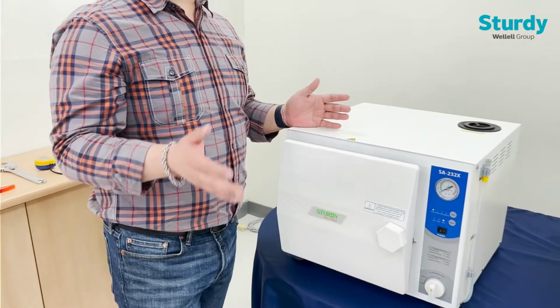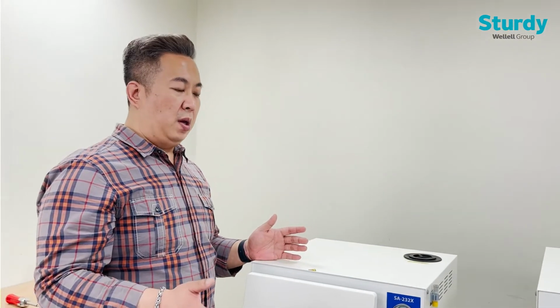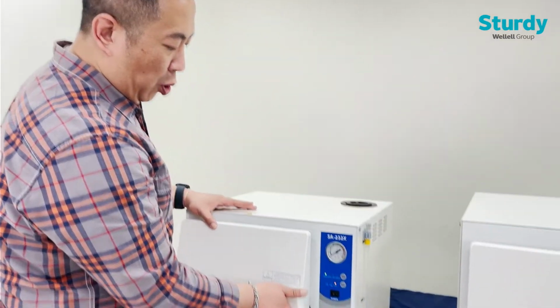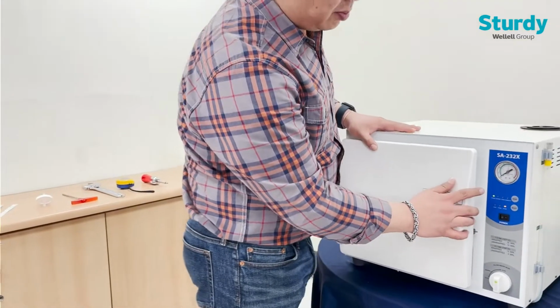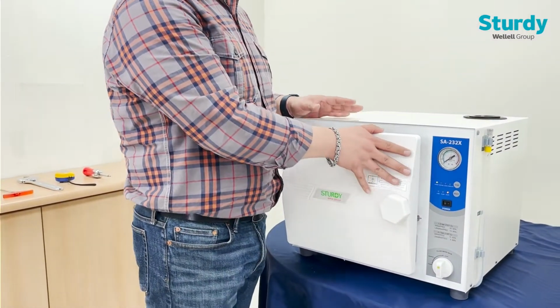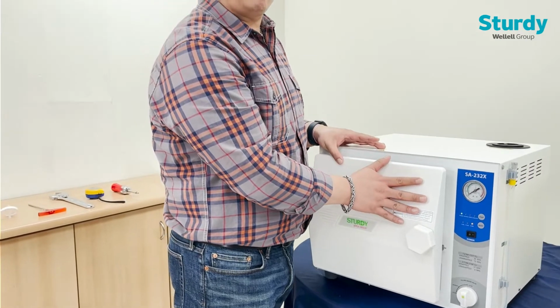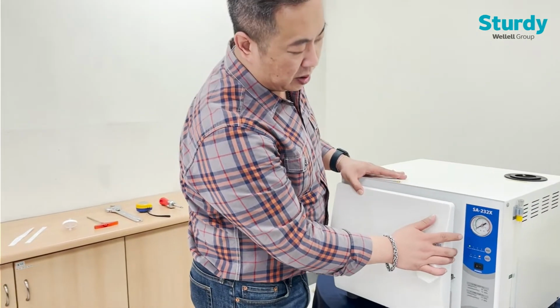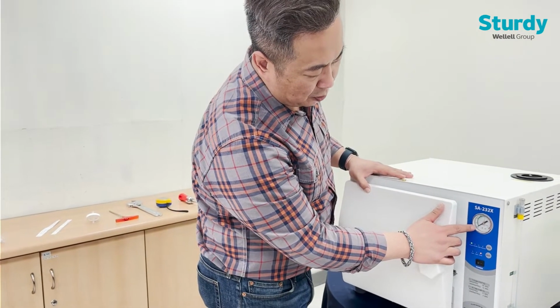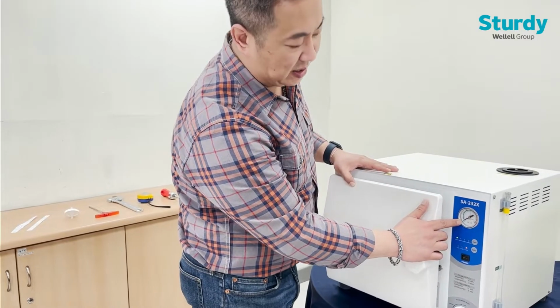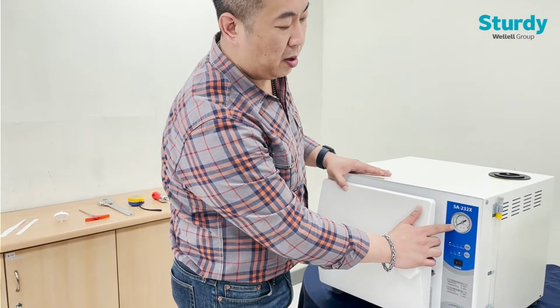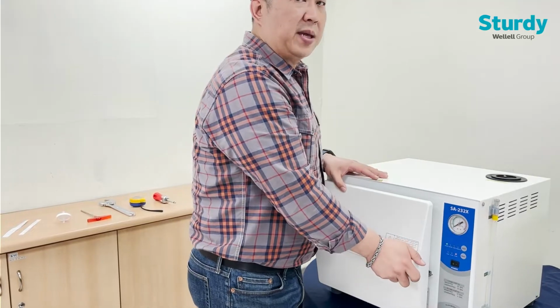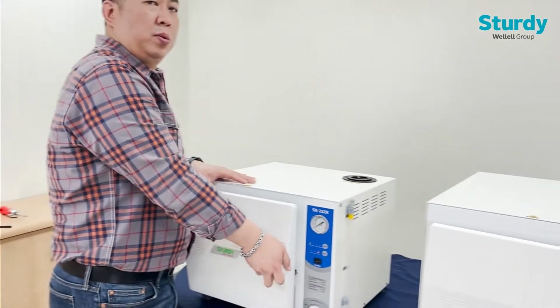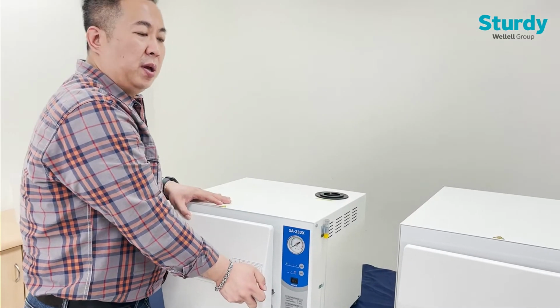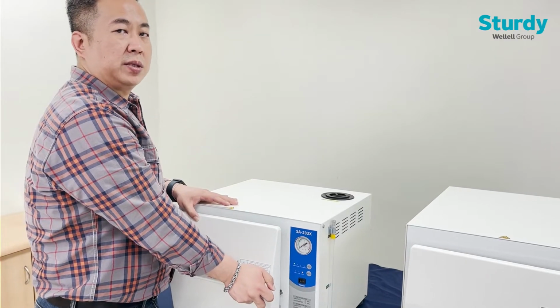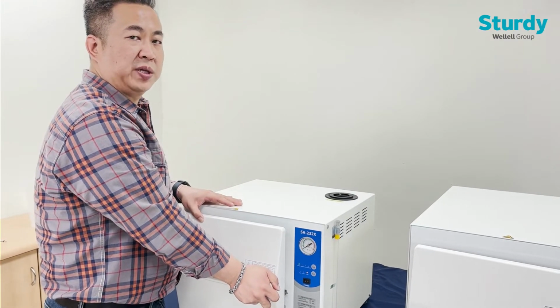At the end of the sterilization process, before opening up the chamber door, please ensure that the internal chamber pressure is at 0. To verify this, we look at the pressure gauge where the indicator is sitting at 0. In the case that the chamber door handle cannot be turned, that means there is still internal pressure inside the chamber.